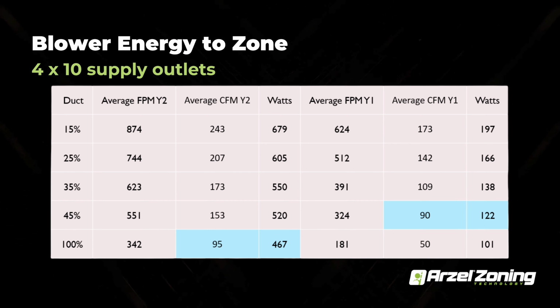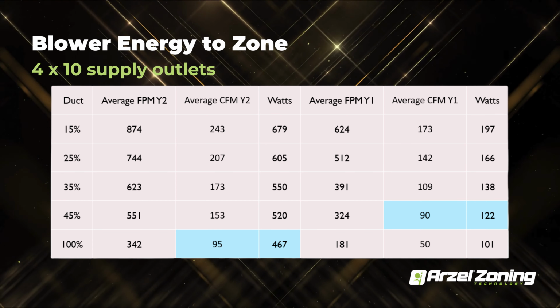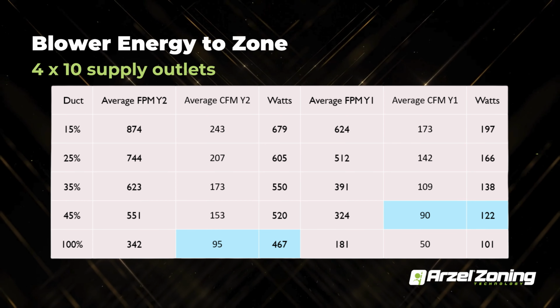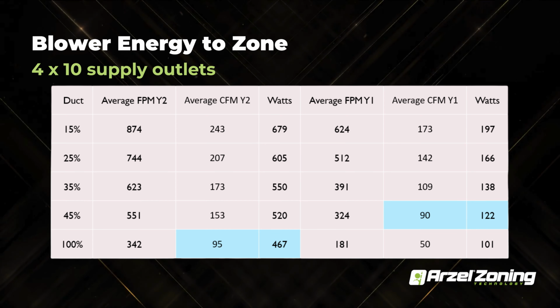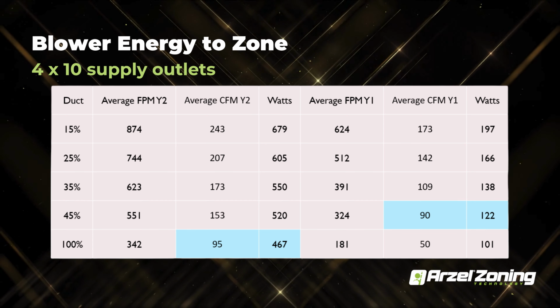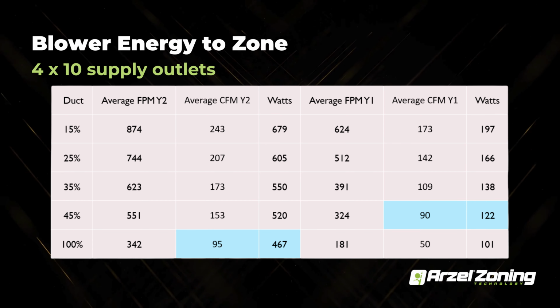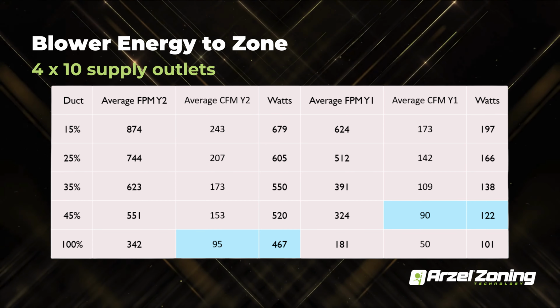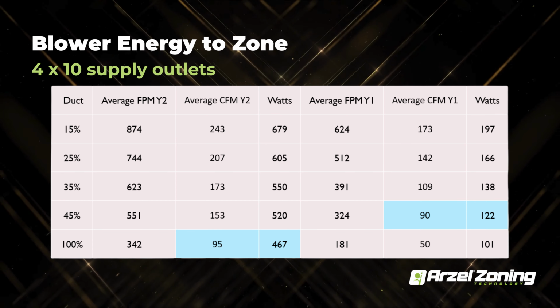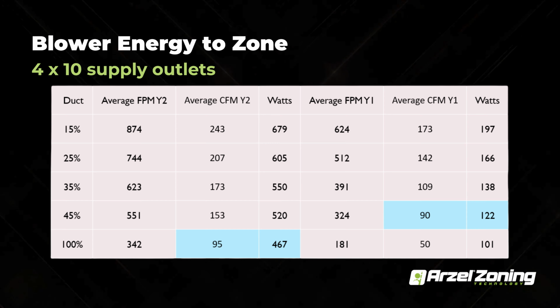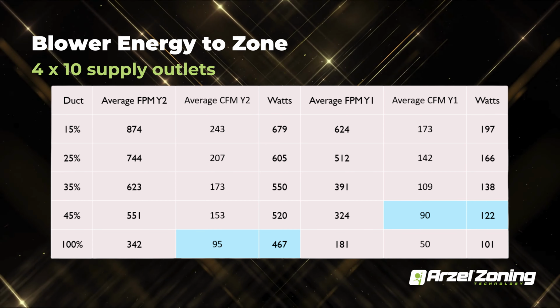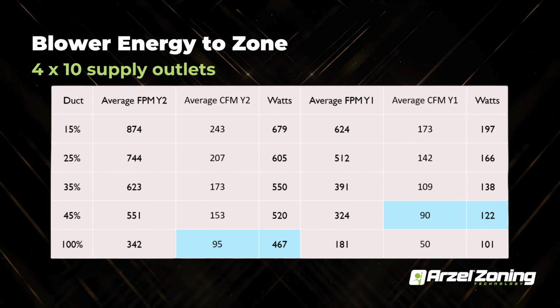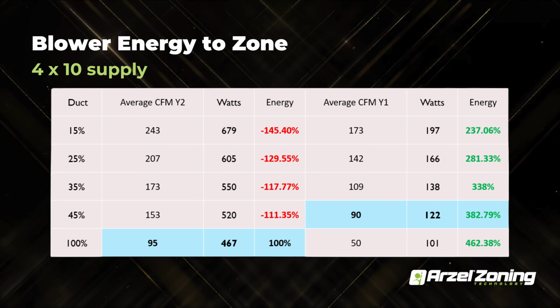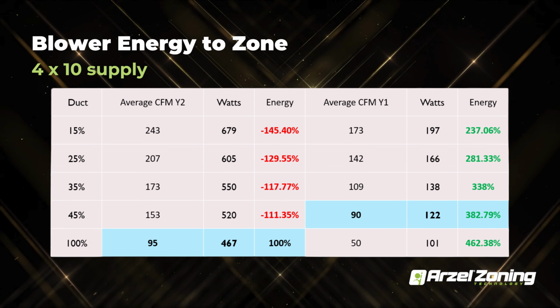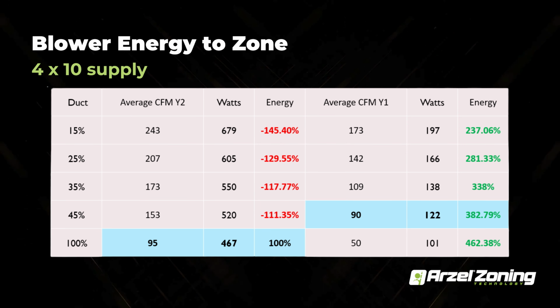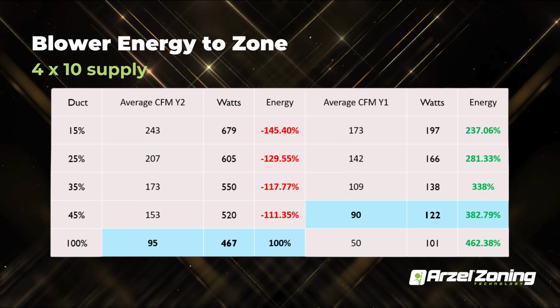On your average CFM for your Y2 on 100% ductwork is 95 CFM. 467 watts is what you're using. So this is 100% of the ductwork open, Y2 outputs on the panel. And then when you are zoning it, if you drop off 50% of that ductwork, just on your single Y1 call, you're able to stay under the wattage of 122 watts. So you essentially achieve the same CFM in those zones, but you get it for a lot less. So zoning does create a little bit of energy efficiency.